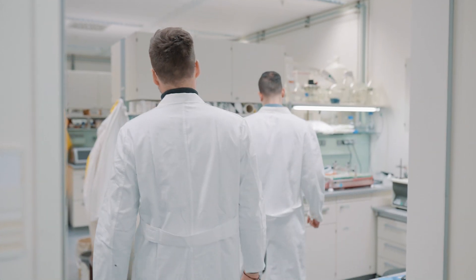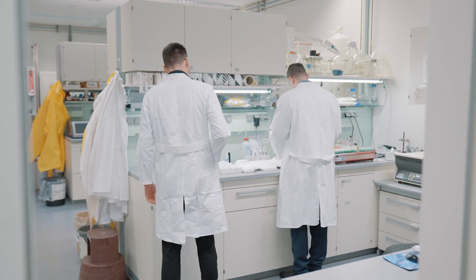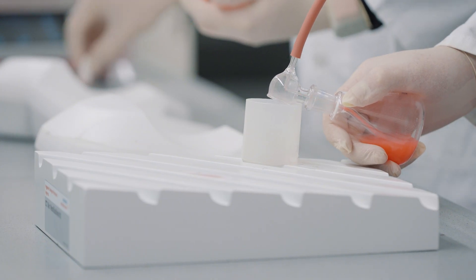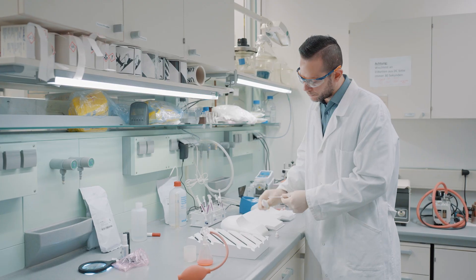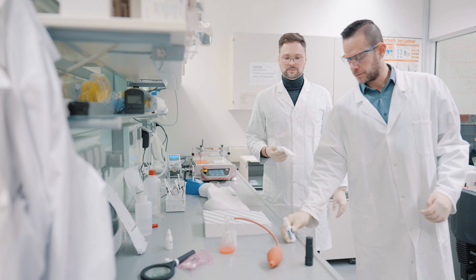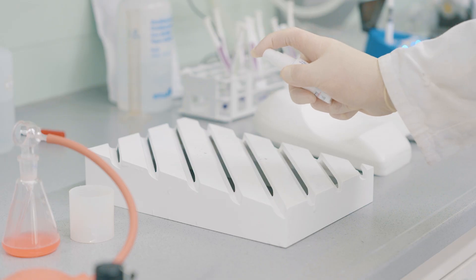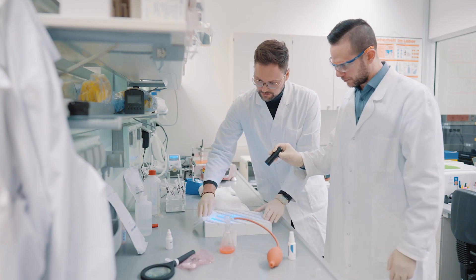The third key area we are focusing on is modern processing technology. The topic complex of processing encompasses three aspects: hygiene technology, hygienic workflow aspects and testing. With our tests, we ensure that all surfaces can be cleaned and disinfected in a proper way. To do this, we use test soils with clinically relevant analytical markers. For simply evaluating the cleanability of the surface, we use a suitable UV-active liquid on the surface. After the cleaning and disinfection procedure, unclean areas remain visible under UV light.